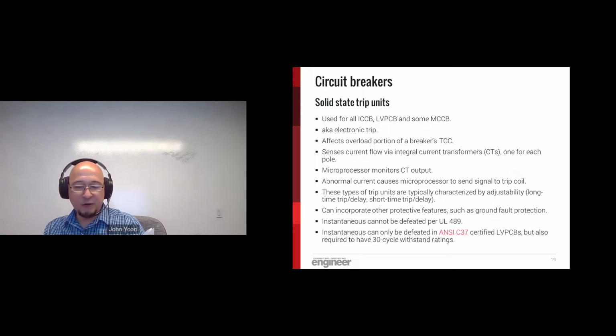Given the various types of scenarios that you may encounter, being able to tweak or make minor adjustments to how that individual breaker reacts to certain conditions can make all the difference in the world. To this end, some breakers can be provided with an electronic trip unit. With electronic trip units, we're replacing a purely mechanical tripping mechanism, like in that picture, with an intelligent module that senses the true RMS current flowing through it with current transformers. Depending on the breaker, you can shape or tweak multiple portions of that time current curve. These trip units sense overcurrent conditions very quickly, but you're limited by the fact that it still has to operate a mechanism to open the circuit.